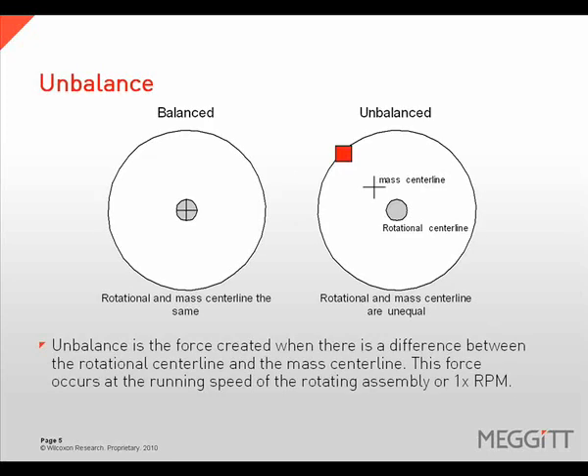Unbalance is the force generated when a difference between a rotational center line and a mass center line exists. This force occurs at running speed of the rotating assembly, or 1 times RPM. The vibration amplitude due to imbalance will increase by the square of the speed. If you double the speed of the rotor, the vibration amplitude due to unbalance will increase by a factor of 4.